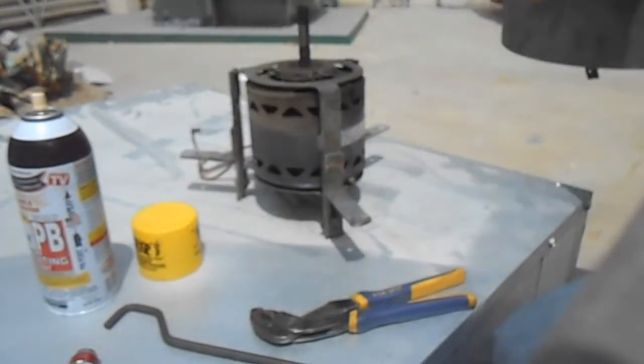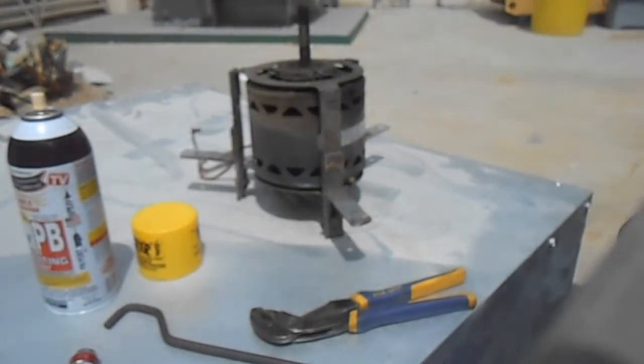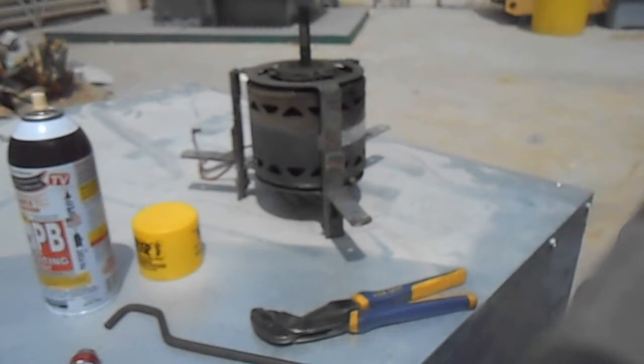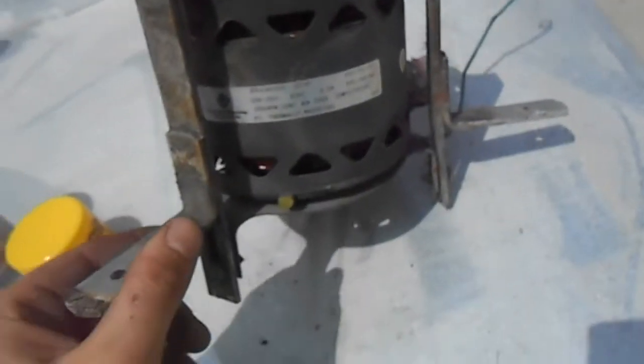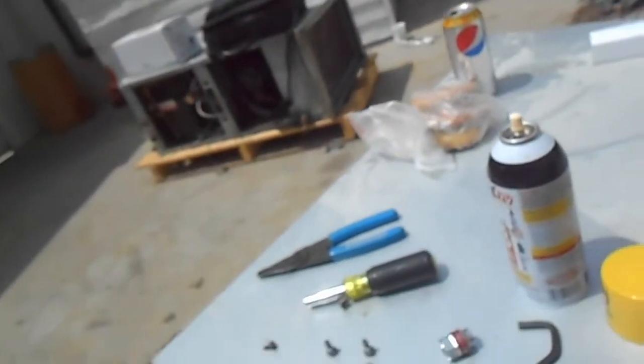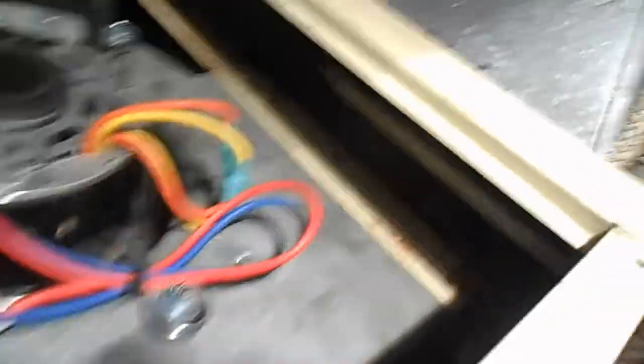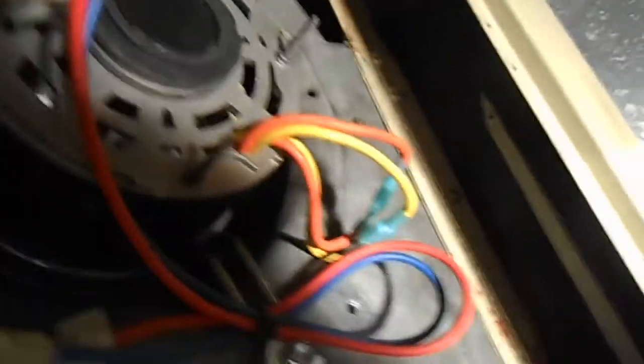All right, there's our motor nice and ready and we take this band off, we put it on the new motor and we're done. Okay my friends, we're all back in there now, our little plate clip back in there. I should have showed you that, but you might be taking those little screws on the bottom apart trying to pull this thing out, but you just take that one 5/16 screw out and that bar pulls out. It's like just kind of a dowel that holds it in there. Anyways, we got our new fan motor and capacitor, started it, tested it, ran no problem.